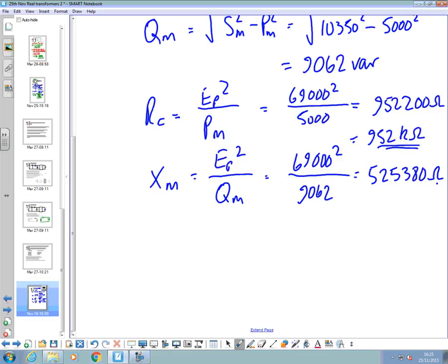Yeah? And then lastly, the transformer ratio, EP over ES, 69,000 over 4160, 16.6.